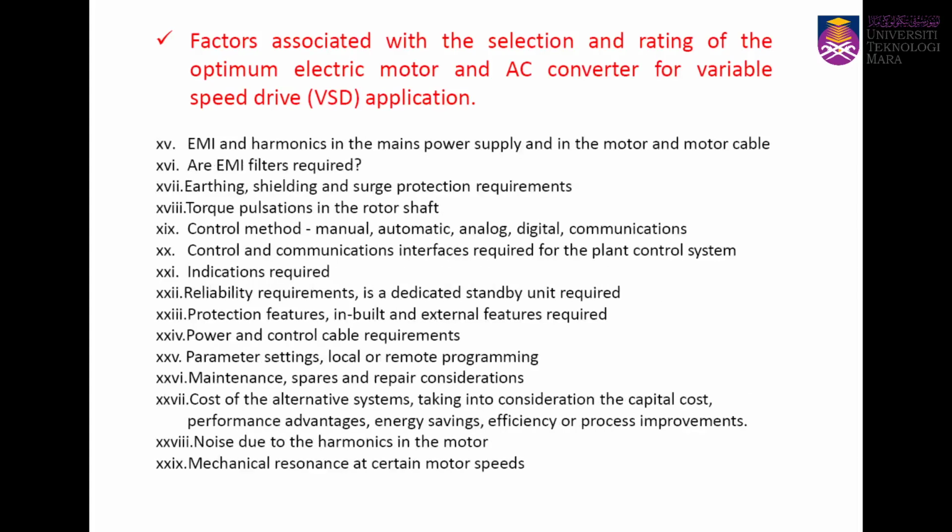EMI and harmonics in the main power supply, in the motor and motor cable. That also needs to be addressed. EMI filters required. If the converter produces high EMI, electromagnetic interference, EMI is electromagnetic interference. Some converters which switch at a very high frequency will actually generate EMI, and sometimes also generate harmonics.